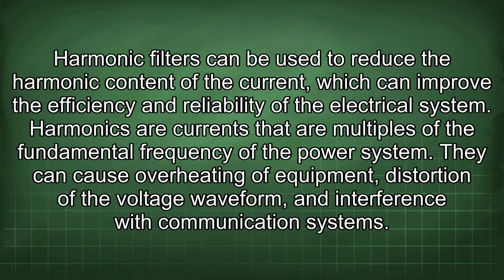Harmonic filters can be used to reduce the harmonic content of the current, which can improve the efficiency and reliability of the electrical system. Harmonics are currents that are multiples of the fundamental frequency of the power system. They can cause overheating of equipment, distortion of the voltage waveform, and interference with communication systems.